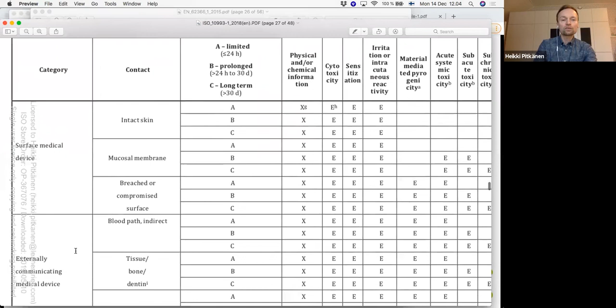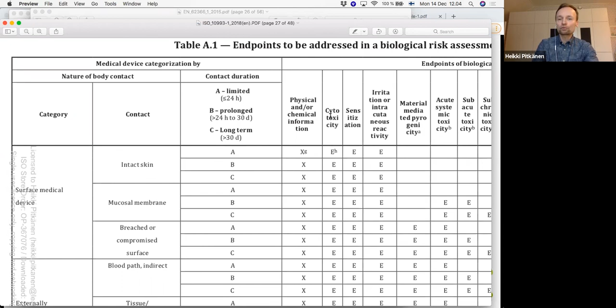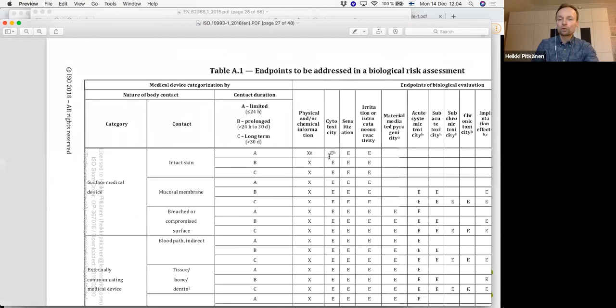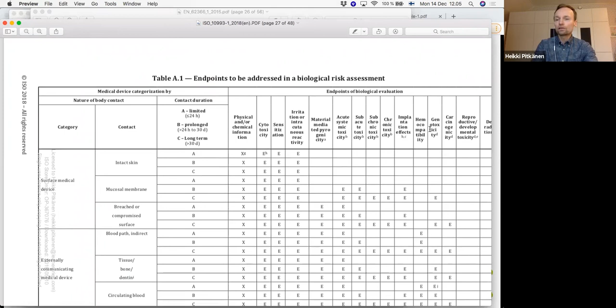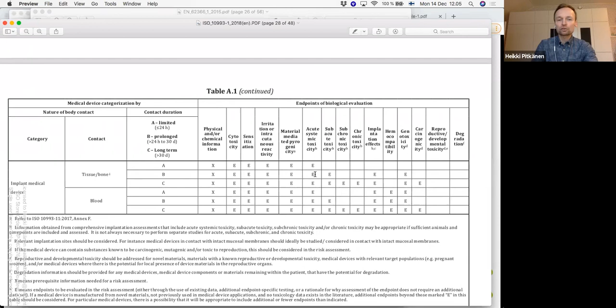Taking all of these into account, the least risky product would come on your intact skin and remain there for a very short time period. For such a product, and for any type of product, you need to do the chemical characterization, and then on top consider those three elements: cytotoxicity, sensitization, and irritation. As you can see, if you go any further from that, into any more serious things, the different parts of the standard series provide you with more things to consider. And when you move into implants, there are a lot of things to take into account.